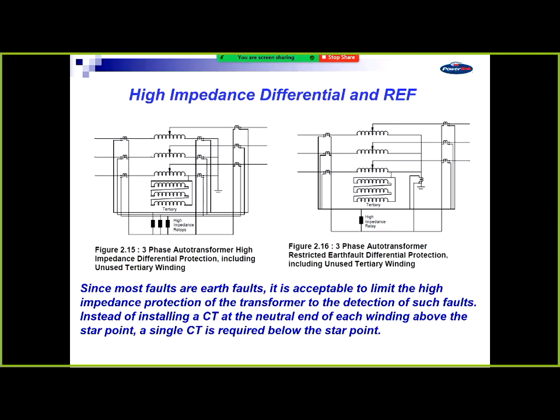If we get an earth fault external to the transformer, it's going to be a lot of current, and we use our bias differential to pick that up. Bias differential needs to cater for CT errors, tapping changes, a whole range of things like that. So it's already got a safety margin built into it. It's not as sensitive for low-level faults. The restricted earth fault will see that. You don't get low-level external faults, you get low-level internal faults.